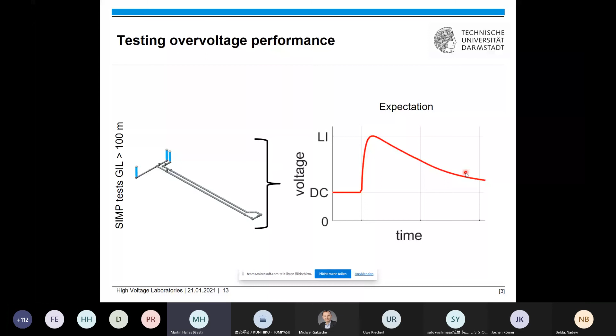So this means you will get some oscillations on your lightning impulse. And why is this like that? Well, for a 100 meters loop, you will get some traveling wave effects. The propagation time for 100 meters would be in the range of 300 nanoseconds. And so you get reflections due to traveling waves across your assembly.